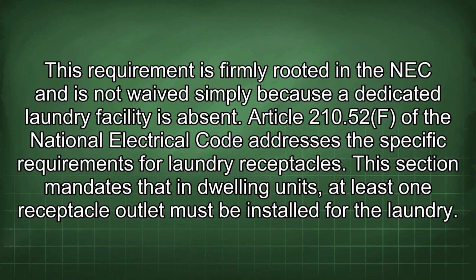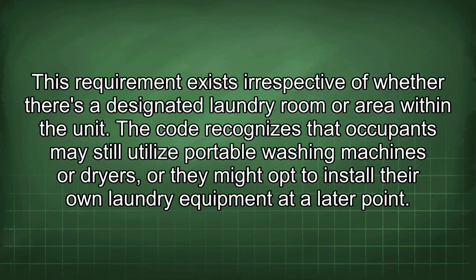Article 210.52(F) of the National Electrical Code addresses the specific requirements for laundry receptacles. This section mandates that in dwelling units, at least one receptacle outlet must be installed for the laundry. This requirement exists irrespective of whether there's a designated laundry room or area within the unit. The code recognizes that occupants may still utilize portable washing machines or dryers, or they might opt to install their own laundry equipment at a later point.